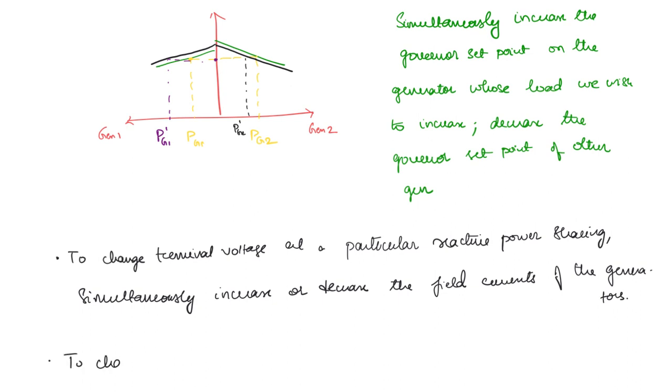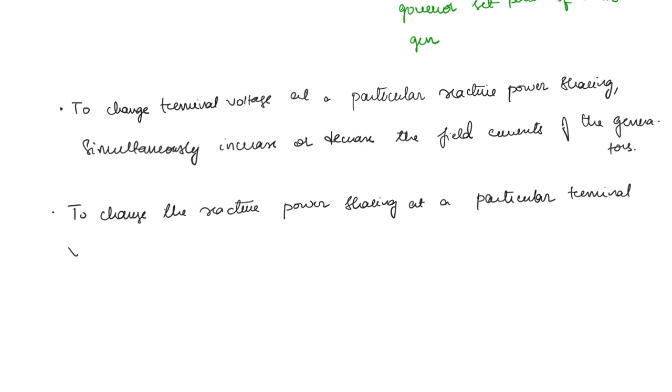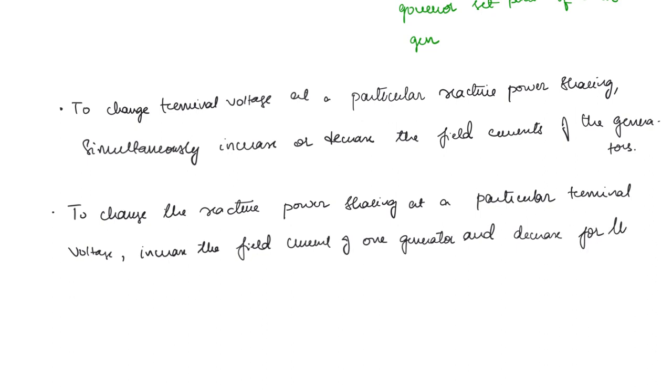Similarly, to change the reactive power sharing at a particular terminal voltage, increase the field current of one generator and decrease it for the other generator simultaneously.